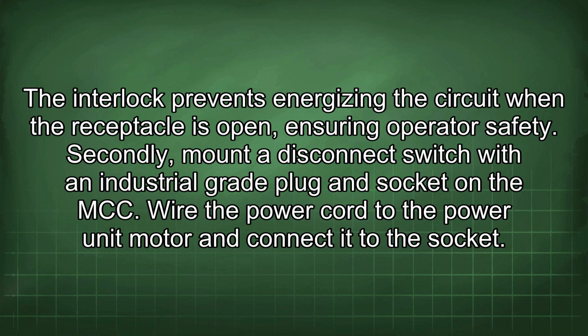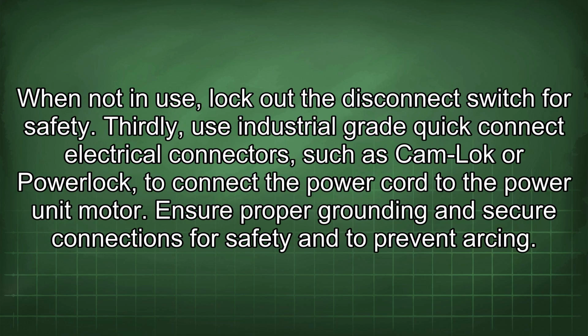Secondly, mount a disconnect switch with an industrial-grade plug and socket on the MCC. Wire the power cord to the power unit motor and connect it to the socket. When not in use, lock out the disconnect switch for safety. Thirdly, use industrial-grade quick-connect electrical connectors, such as Cam-Lok or Powerlock, to connect the power cord to the power unit motor. Ensure proper grounding and secure connections for safety and to prevent arcing.